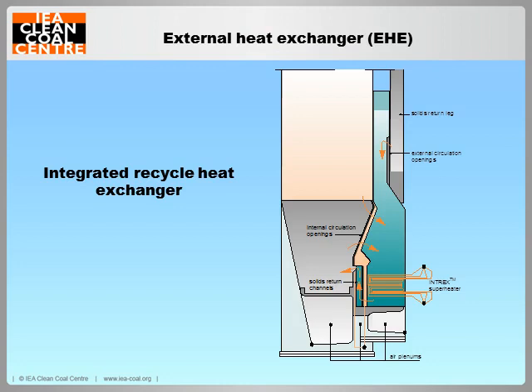Bubbling fluidized beds are normally used to extract heat from the hot circulating solids collected by the cyclones. The major advantages of using an external heat exchanger are its ability to adjust the superheat and reheat steam temperature and to control the combustion temperature. This figure shows an integrated recycle heat exchanger developed by Foster Wheeler.